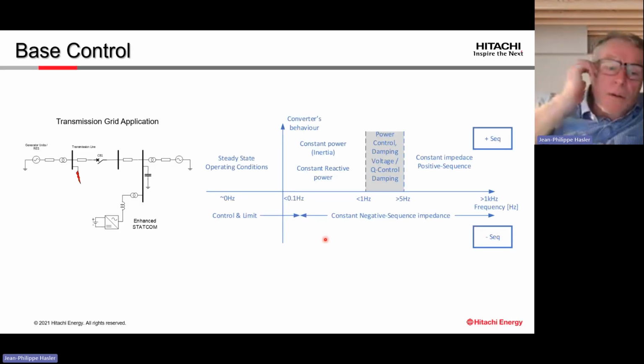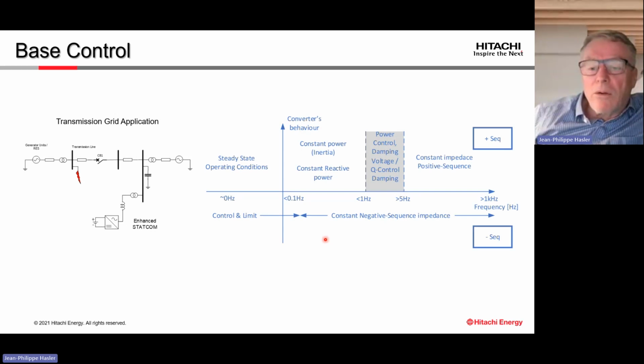A basic control. For the basic control of a STATCOM, I think we have to differentiate the control behavior in different zones. And we define a zone regarding the positive sequence, how it should react when we have a disturbance in the positive sequence, but also the negative sequence, how it reacts, especially how the STATCOM will react when we have a fault in the grid, which can be a one-phase or two-phase fault disturbance.